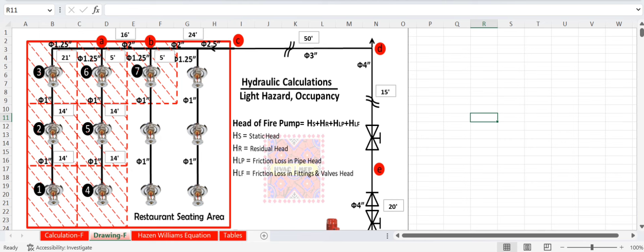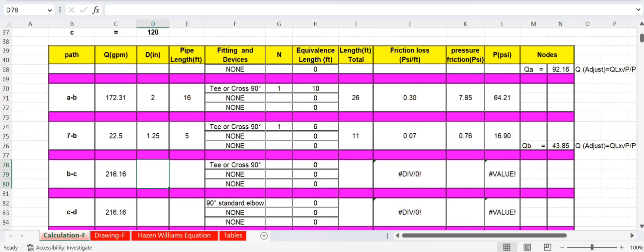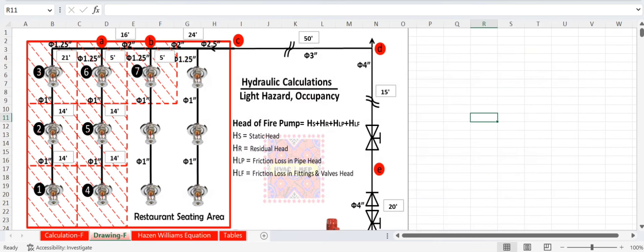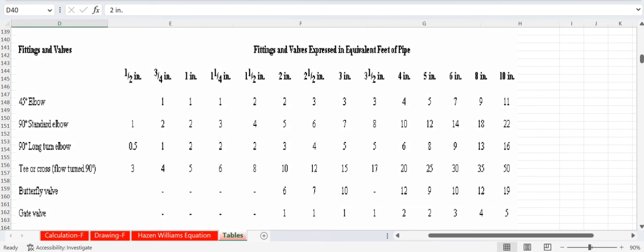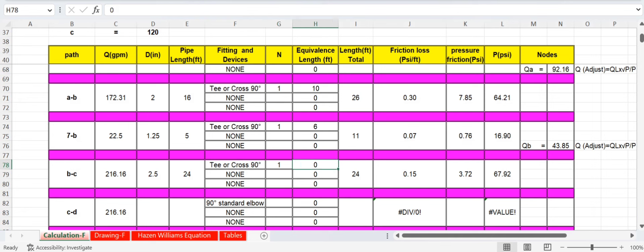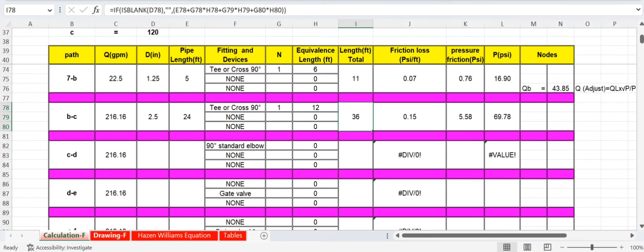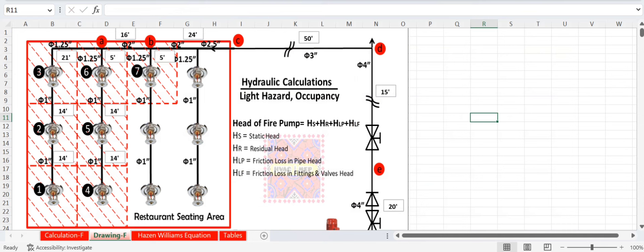Path B→C fittings: one T-fitting for 2.5-inch pipe. From the table, equivalent length for 2.5-inch T = 12 feet. Total length = 24 + 12 = 36 feet. Friction loss and total pressure are calculated accordingly.